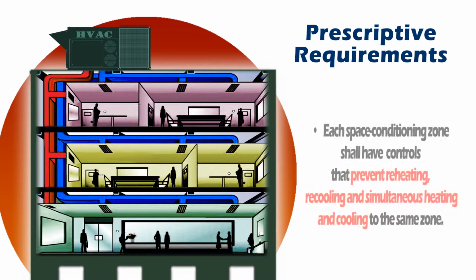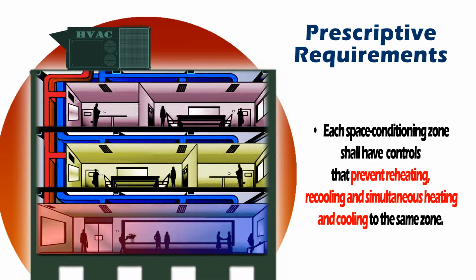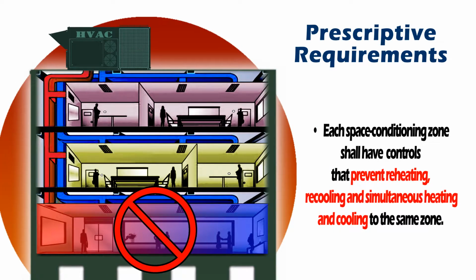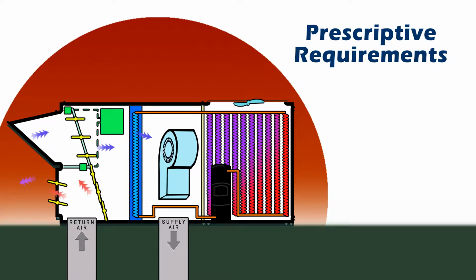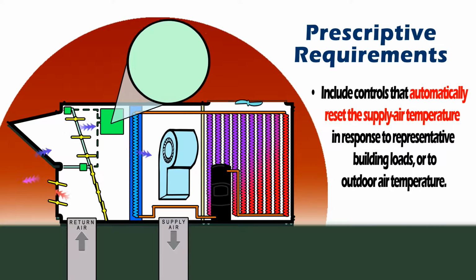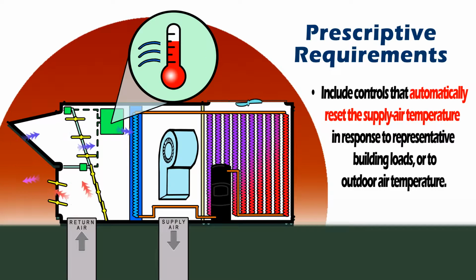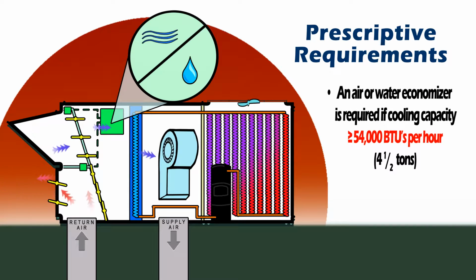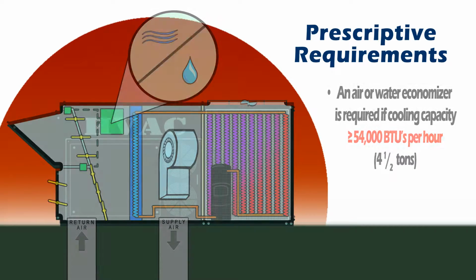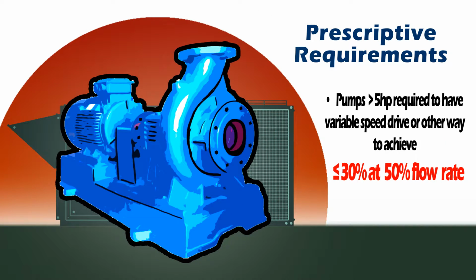Each space conditioning zone shall have controls that prevent reheating, recooling, and simultaneous heating and cooling to the same zone. HVAC systems supplying heated or cooled air to multiple zones must include controls that automatically reset the supply air temperature in response to representative building loads or to outdoor air temperature. An air or water economizer is required for each HVAC system that has a cooling capacity greater than 54,000 BTUs per hour, or approximately 4.5 tons. And finally, pumps serving variable flow systems that are greater than 5 horsepower are required to have a variable speed drive or other way to achieve no more than 30% power at 50% flow rate.